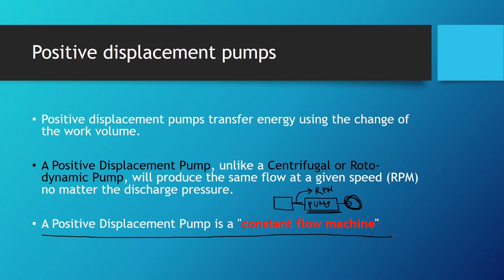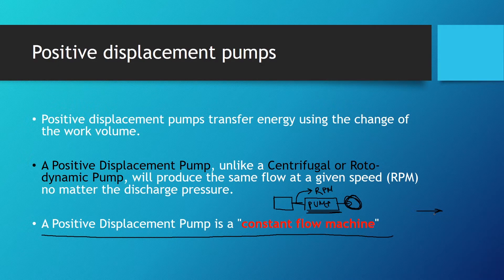One negative aspect of positive displacement pumps is that we always need a safety valve. Why? Because a positive displacement pump operating against a closed discharge valve continues to produce flow until the pressure in the discharge line increases to the point where the line bursts or the pump is severely damaged — or both.